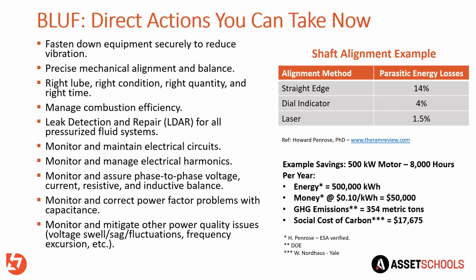Increasingly, and until Howard Penrose told me about this, if somebody would have told me this, I wouldn't have believed it. He said what we need to be doing is using passive filtration on our ground and neutral loops. And I said, ground and neutral loops, you shouldn't see energy on your ground or neutral loops. He says, yeah, but you do when you have nonlinearity in your loads. And he showed me an example where the ground loop was showing milliamps of energy on the ground. And he said, what impact do you think that's going to have? I said, I don't think that's going to have any impact at all. Maybe a fraction of a % impact.